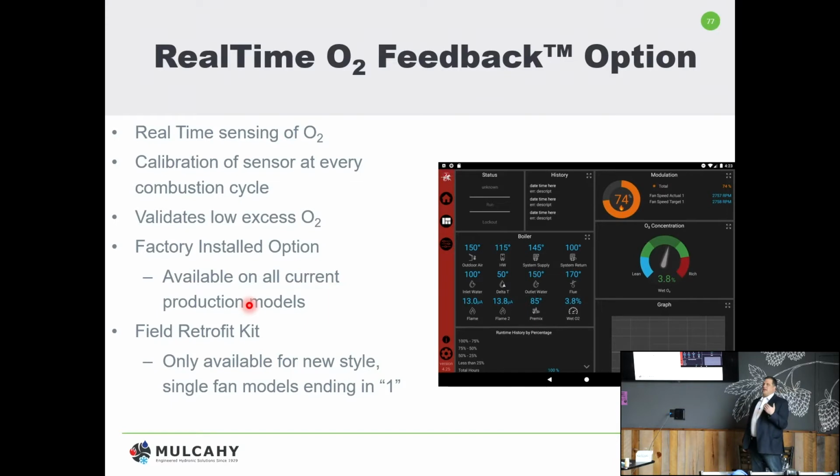It'll time sequence the run times to match the systems. So some other things that you can add in the systems, and I bring this up, is that some people are obsessed. If you really, really want to get good at condensing boilers, what you actually maintain is a tight O2 in the combustion chamber. So you maintain really good tight O2. Well, things that can influence that are air quality, gas quality, and stuff like that.